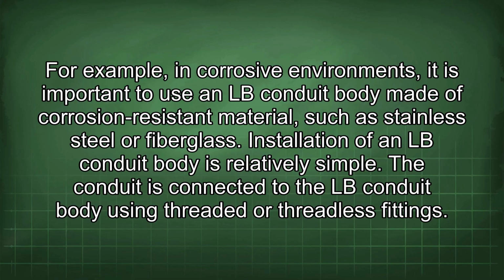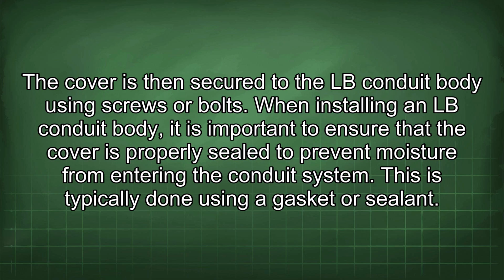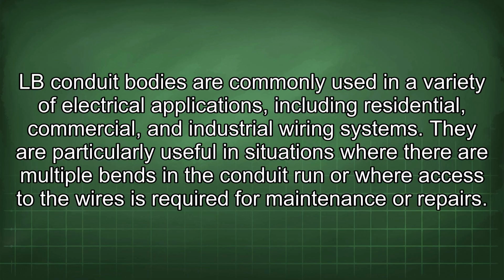The conduit is connected to the LB conduit body using threaded or threadless fittings. The cover is then secured to the LB conduit body using screws or bolts. When installing an LB conduit body, it is important to ensure that the cover is properly sealed to prevent moisture from entering the conduit system. This is typically done using a gasket or sealant. LB conduit bodies are commonly used in a variety of electrical applications, including residential, commercial, and industrial wiring systems. They are particularly useful in situations where there are multiple bends in the conduit run or where access to the wires is required for maintenance or repairs.